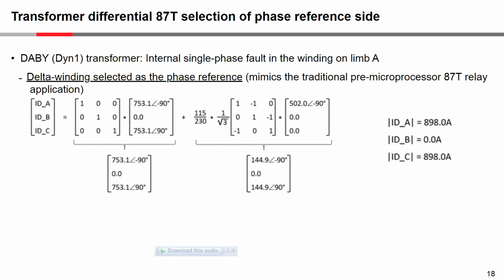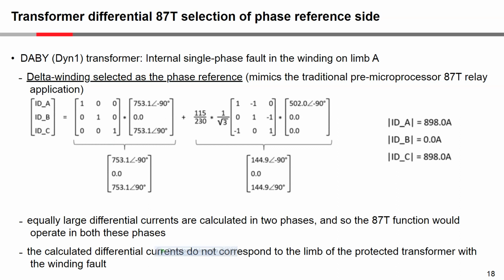Firstly, we look at the delta side selected as the phase reference. So this would be the selected matrix for that, and this would be the matrix that would need to be put on the Y side. Here are the primary currents. And if you make the calculation, you can see that we'd have equally large differential currents in two phases. And so the 87T would operate in both these phases. Also we can see that the calculated differential currents would not correspond to the limb of the fault, because we would get equal currents in two phases.